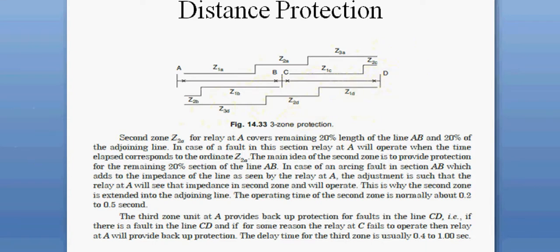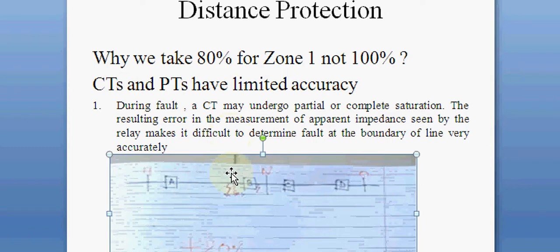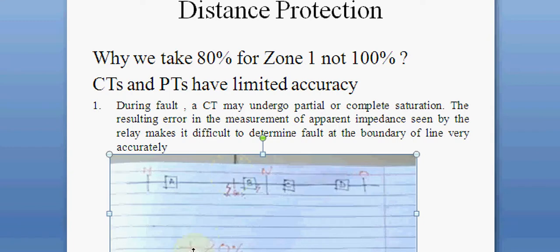Why do we take only 80% of the line length for Zone 1? During a fault, a CT may undergo partial or complete saturation. The resulting error in the measurement of the apparent impedance seen by the relay makes it difficult to determine faults at the boundaries of the line very accurately. The inputs to the relay are provided by CTs and PTs, and considering saturation errors, the maximum error can be up to ±20%.